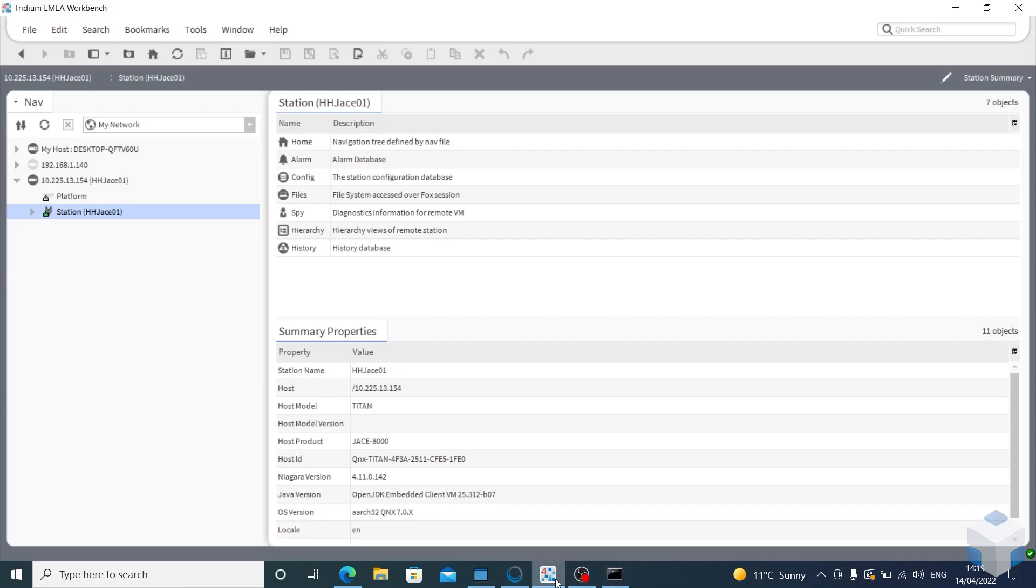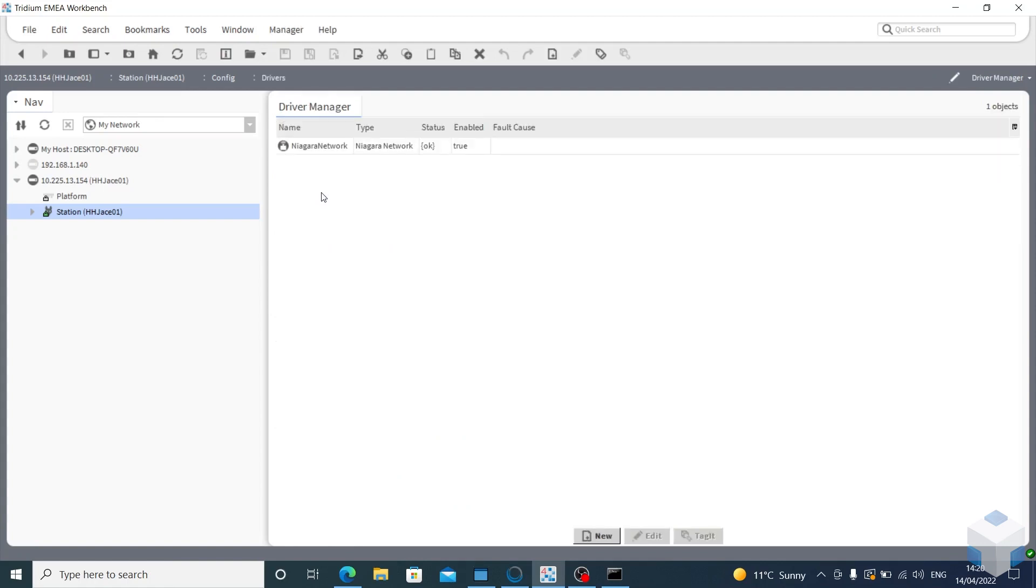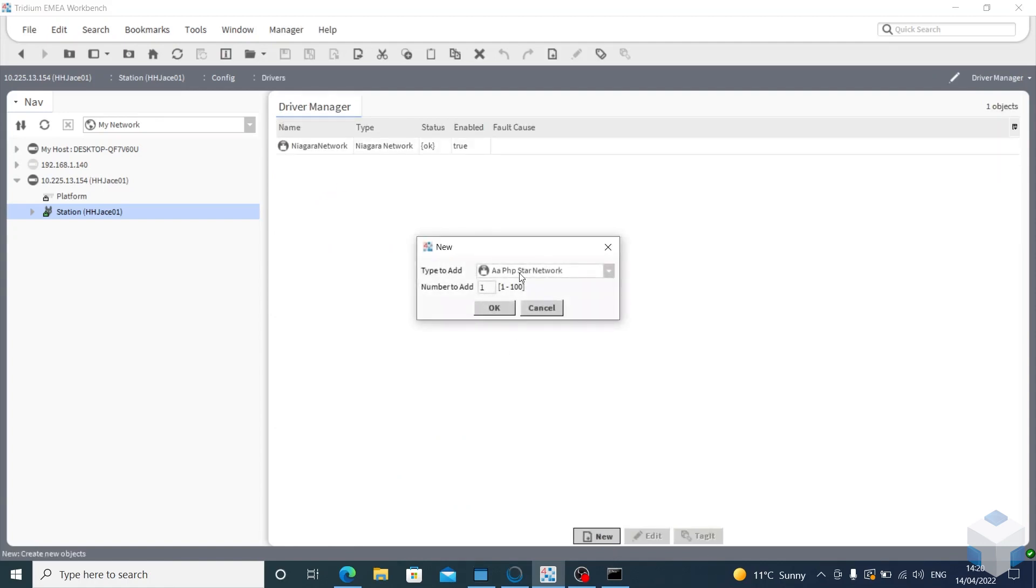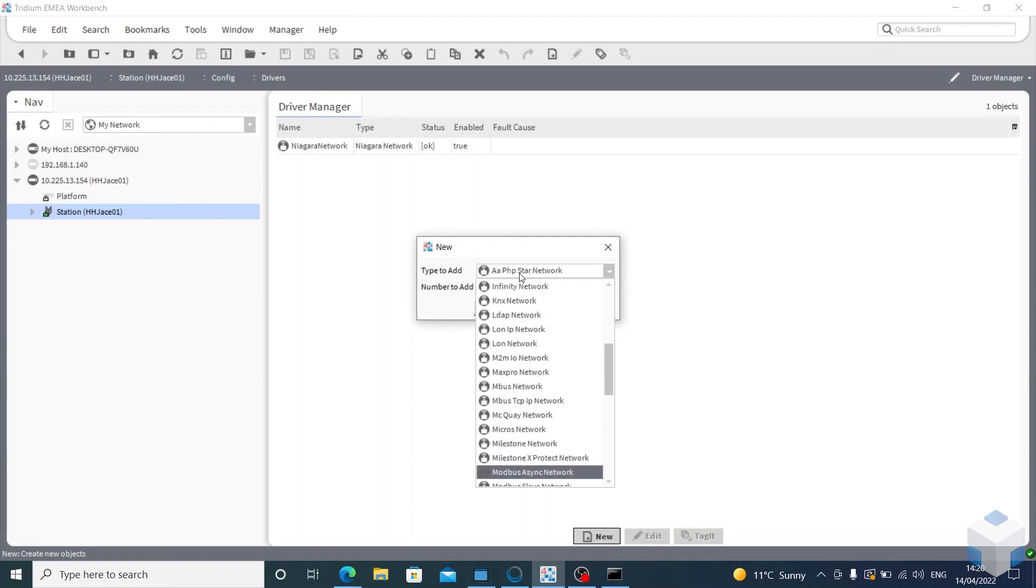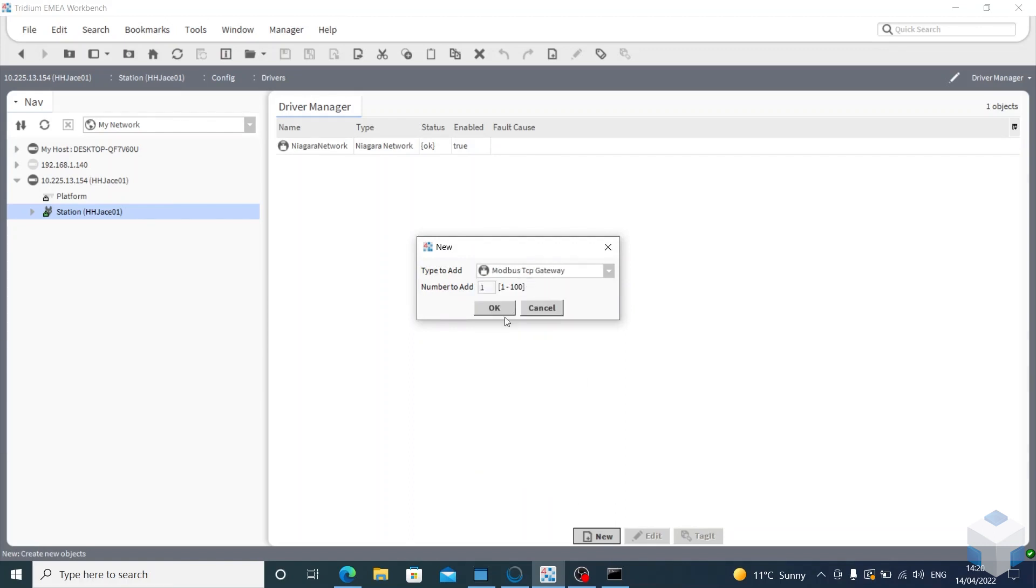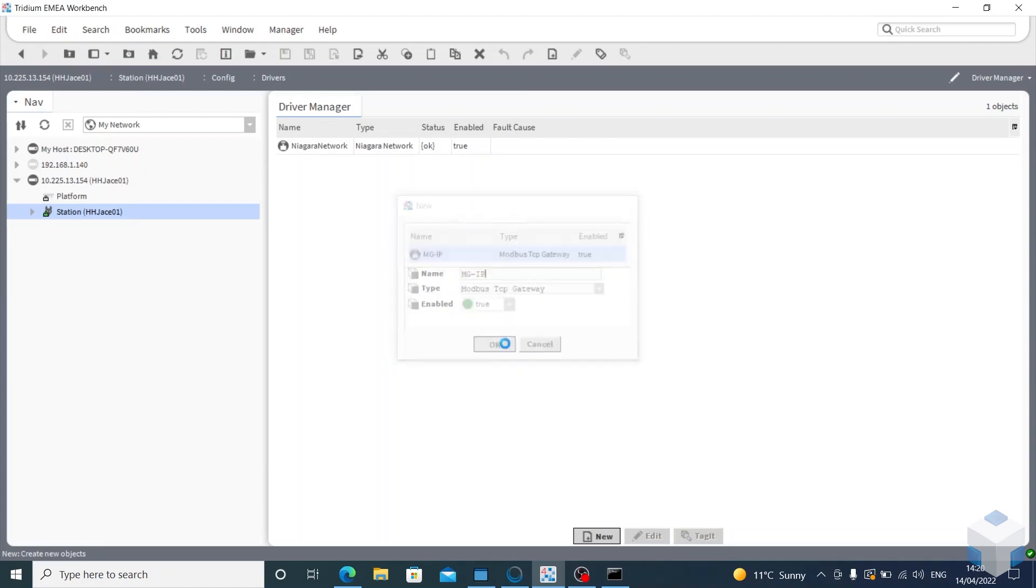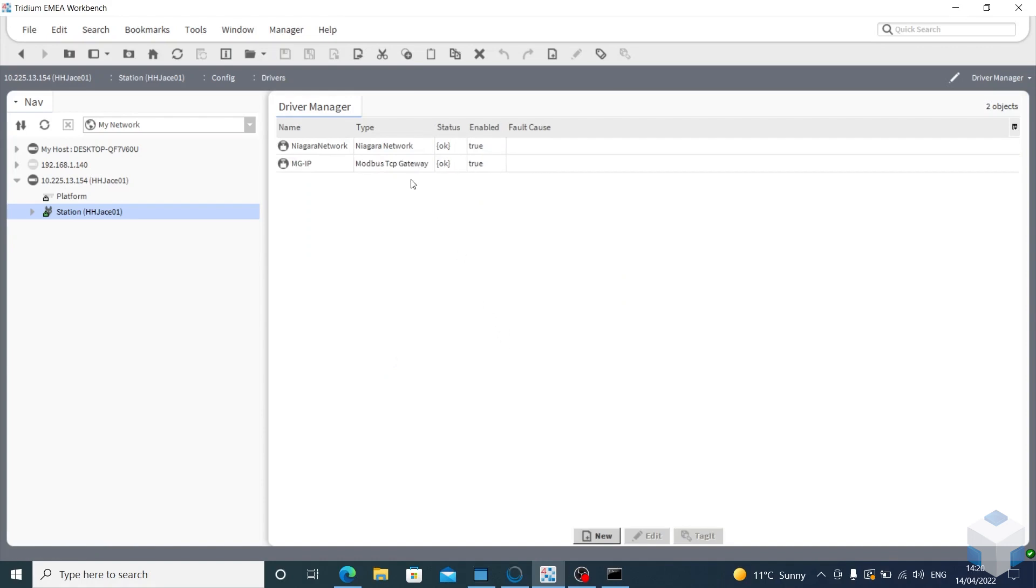From here you want to go to Niagara, and then on the controller that you want to pull this MGIP onto, you want to go to config drivers. Then we want to add Modbus TCP gateway. If we go to Modbus, there it is. Add one, and then we'll name this MGIP, click OK.